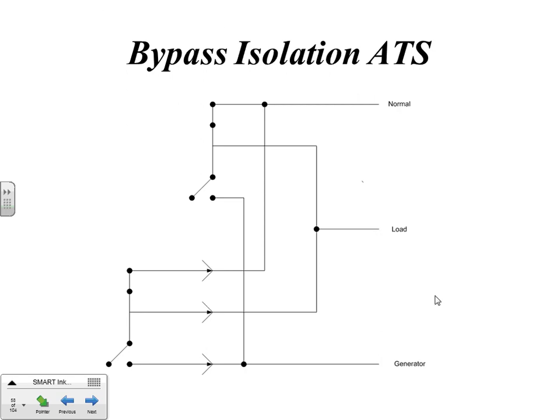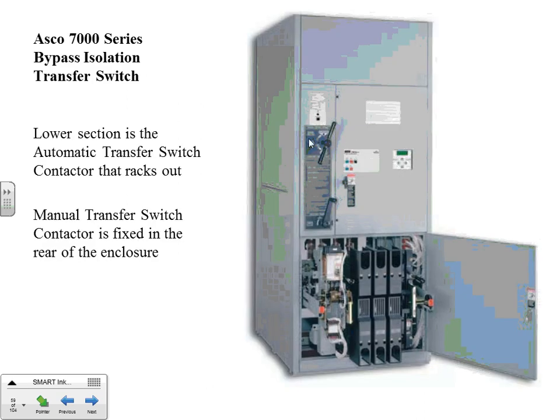Jimmy, the top one will be the manual then? Top one is the manual switch. So if there were an issue with the automatic and something happened, we could actually rack this one out and manually switch this. And there's a picture I'll show you on the next slide. This is actually the manual switch operator here. And this is the rack crank to bring out. You'll see the actual rack. You can actually pull the automatic switch right out of the bottom.